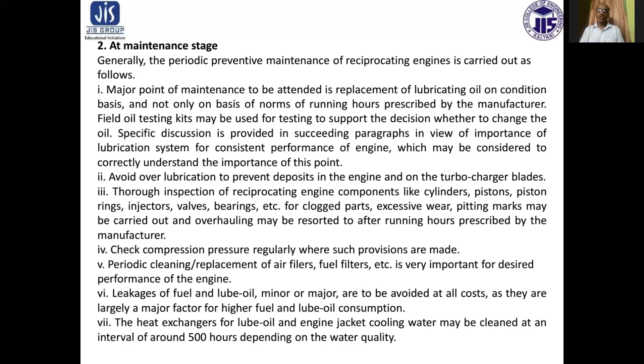Number 6, leakage of fuel and lube oil, minor or major, are to be avoided at all costs, as they are largely a major factor for higher fuel and lube oil consumption. Number 7, the heat exchangers for lube oil and engine jacket cooling water may be cleaned at an interval of around 500 hours depending on water quality.